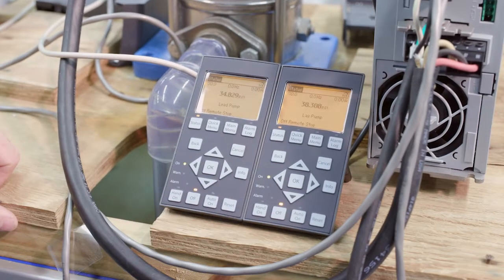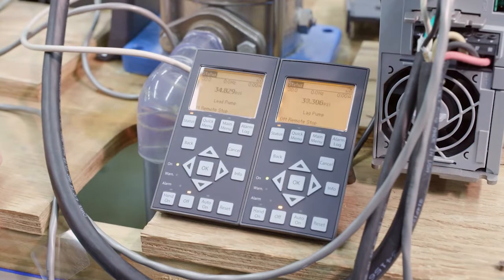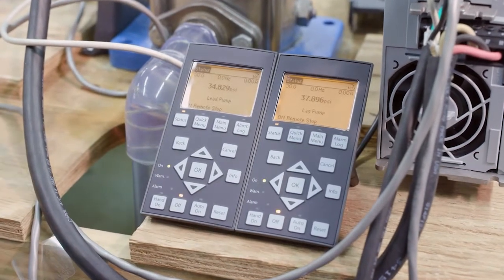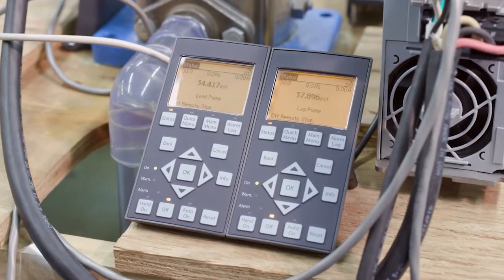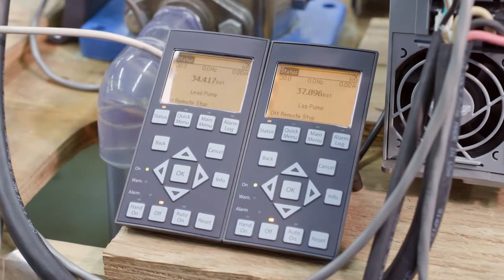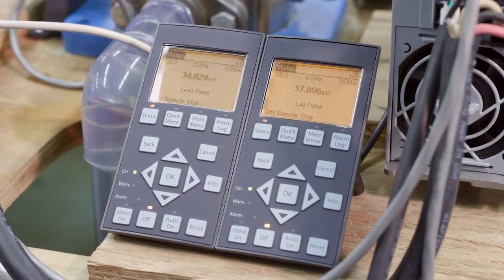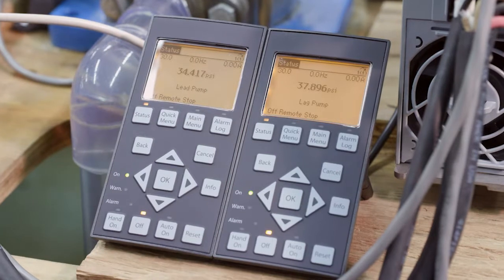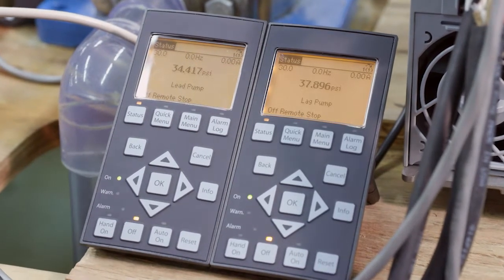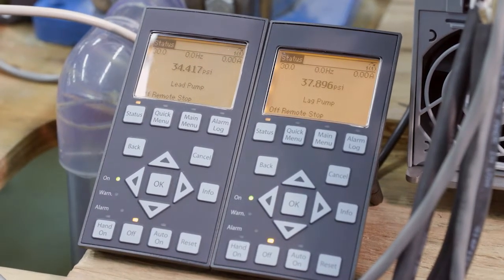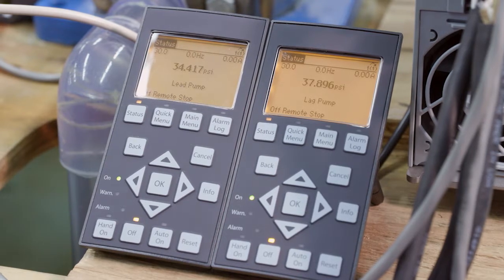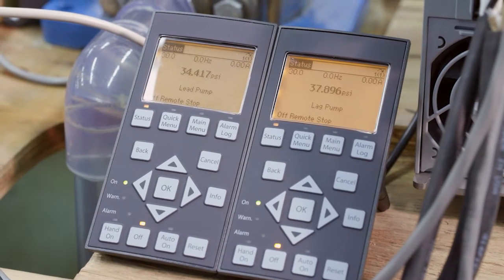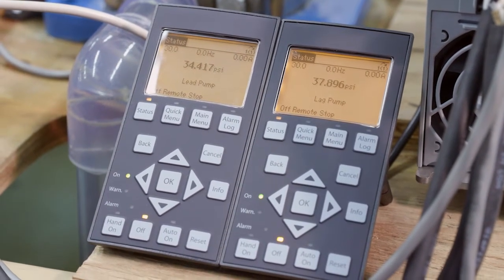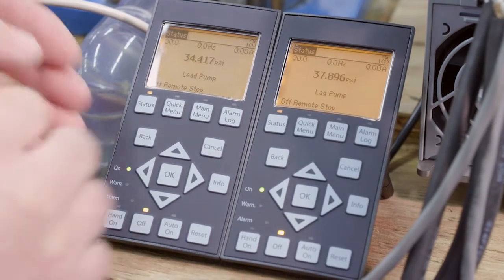Now let's put these units into Synchronous, which is what we have on the IPC Basic. So Synchronous basically means that in this case we have a duplex, so when pump 2 comes on, both pumps will be operating at the same speed. So let's go in here and change both to Synchronous and run both of them.